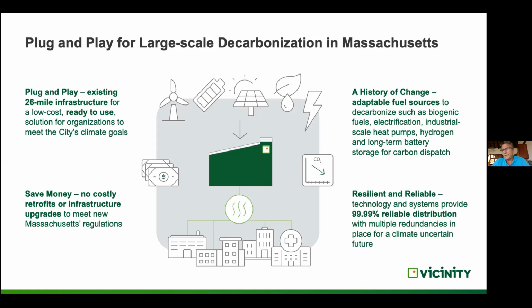But with some of these very new industrial-scale heat pumps, using refrigerants like hexane or pentane, we can do that in an industrial facility. You're not going to have those refrigerants in a commercial office tower, but we can do it industrially. So next we're going to look at a large heat pump to preheat our feed water in our combined heat and power plant.